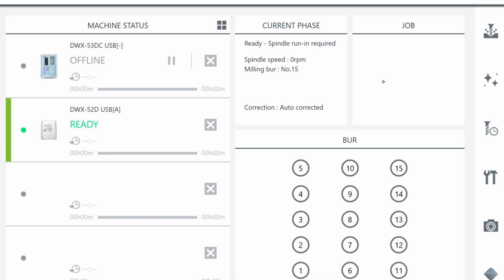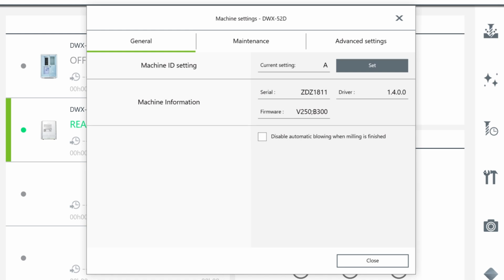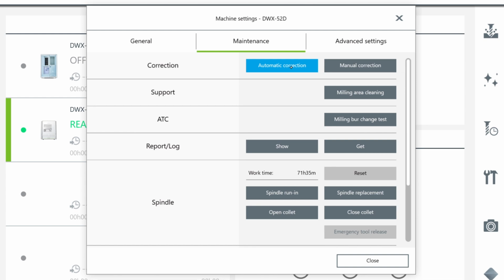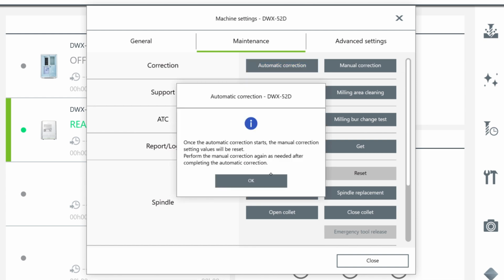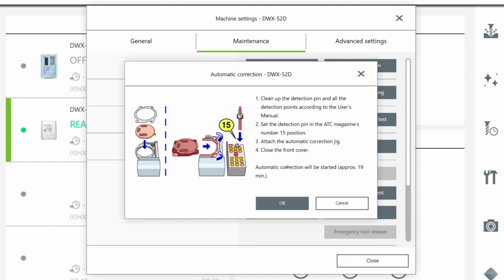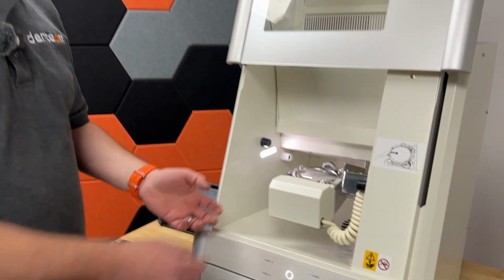Yep. All right, so we're in V-panel, pretty dang straightforward. You're going to go into your maintenance section, hammer and wrench, bring it up, maintenance, and then we're going to go automatic correction. Read and pay attention to the prompts. It's essentially telling you to do what I just said, but it's a little less detailed. Hit OK. The machine will do its thing. It takes about 20 minutes. And once it's done, then you're ready to go and start milling. All right, it's been 20 minutes. We're done. We got a successful calibration.